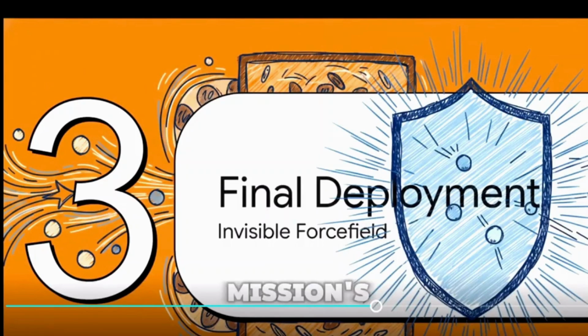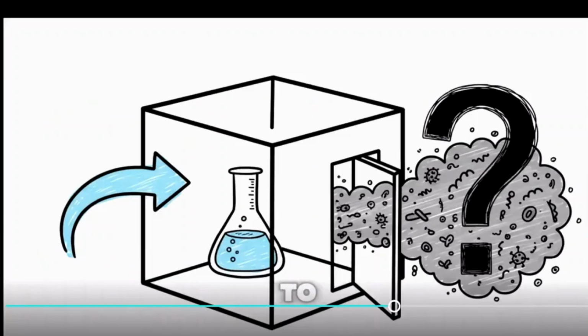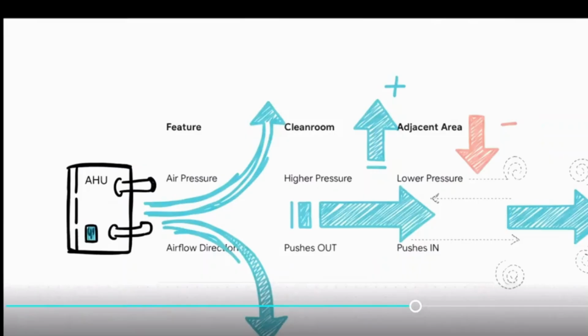But hold on, the mission's not quite over yet. Being pure is one thing. Staying pure and actually protecting the room, that's the final and kind of genius step. Let's check it out. It's not enough to just pump ultra-clean air into a room. Think about it: what happens every time someone opens the door? All that less clean air from the hallway is going to try to rush in, right? Well, the system has a very clever solution for exactly that problem, and it's all about pressure.